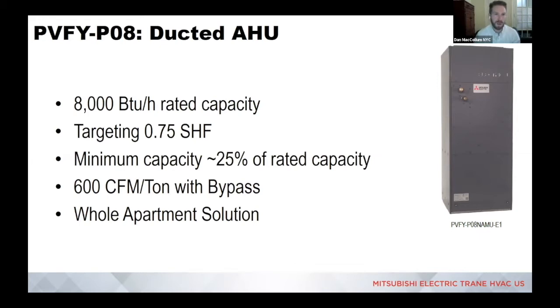It was thought about as serving the entire apartment, specifically for a passive house building. And when you start looking at passive house versus standard applications, if you will, the load profile versus the square footage is drastically different. So we wanted to make sure that this unit was moving enough air so that it could adequately reach and condition such a large space that 8,000 BTUs are going to.